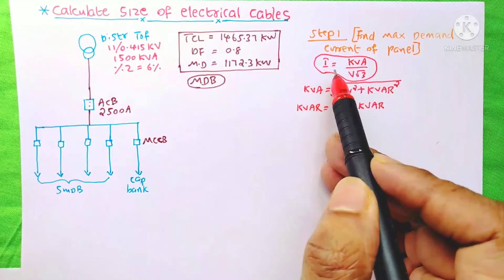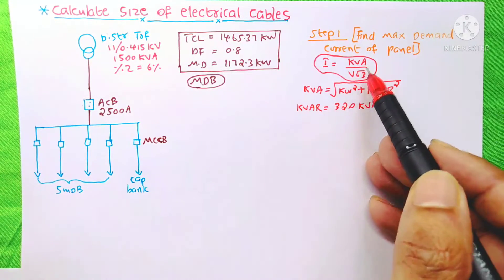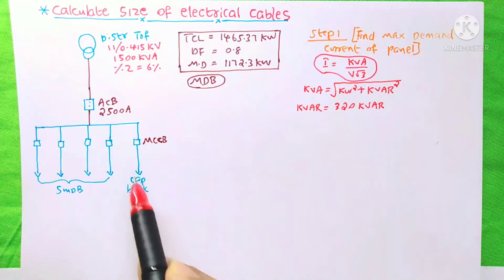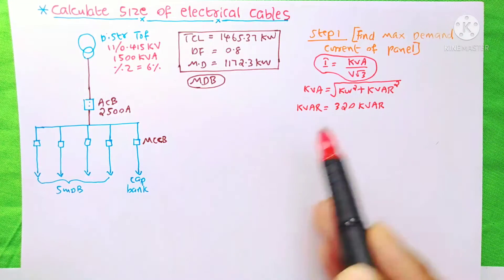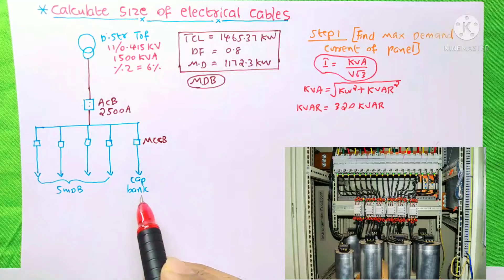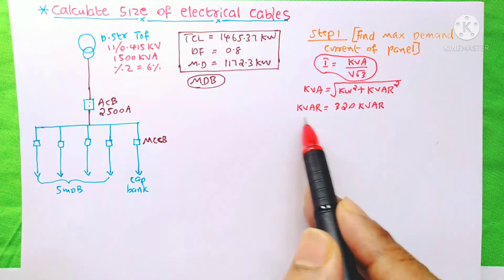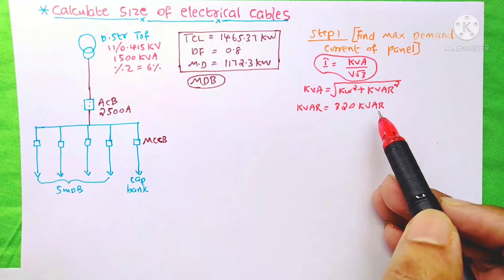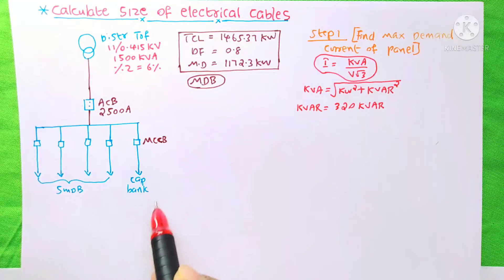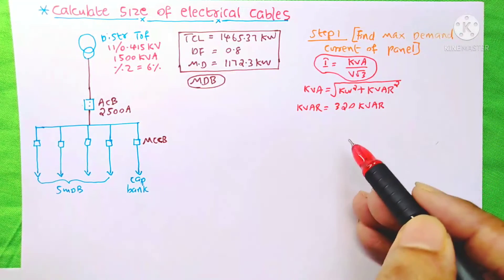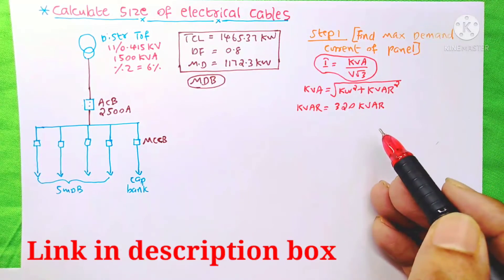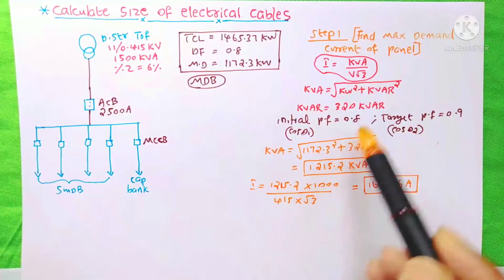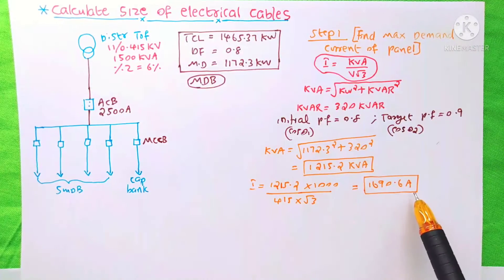The equation is: I = P / (V × √3), and here KVA = √(KW² + KVAR²), because for this MDB we have a capacitor bank, so to size this cable we need to consider the capacitor bank as well. The KVAR is equal to 320 KVAR. The answer is 1215.2 KVA, and substituting into the first equation, the answer is 1690.6 A.